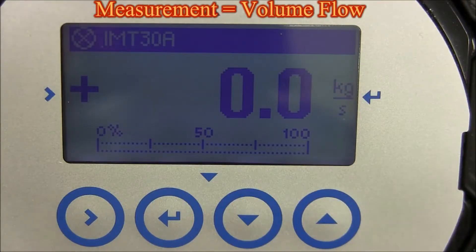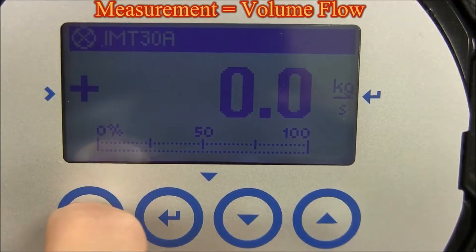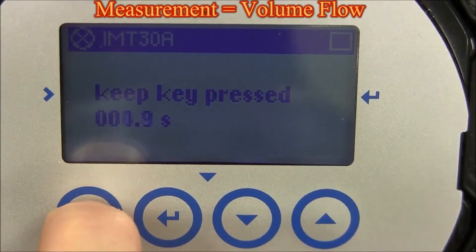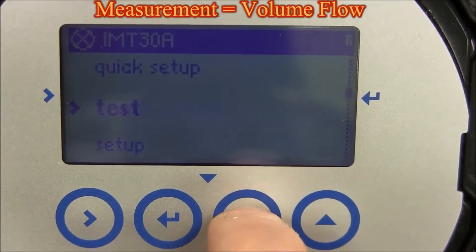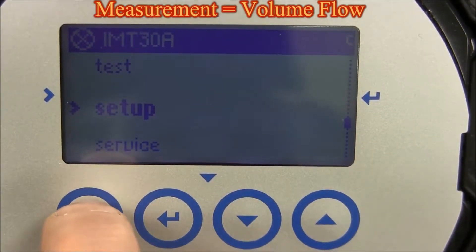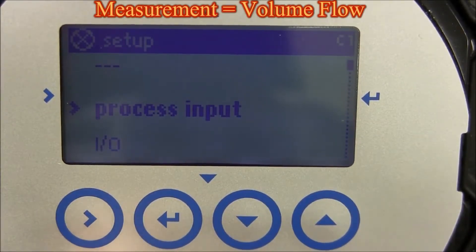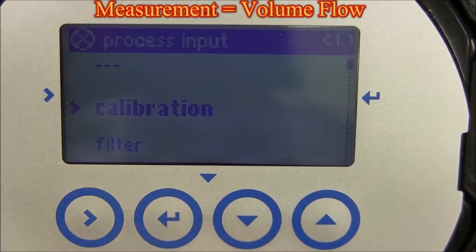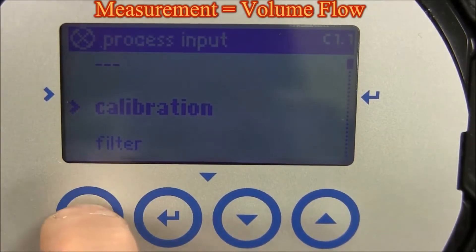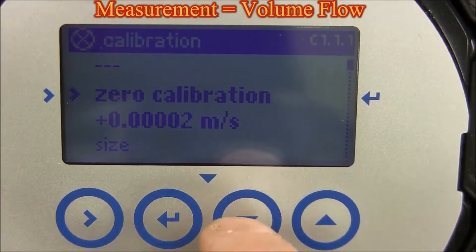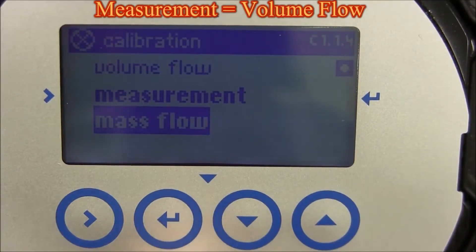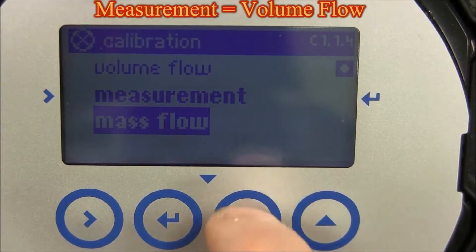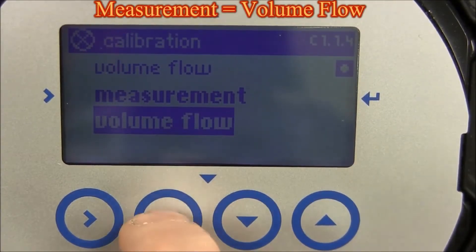To select volume flow for the measurement parameter, press and hold the right arrow for three seconds, then let go. Press the up or down arrow until setup appears, then press the right arrow. Press the right arrow to go into process inputs. Press the right arrow to go into calibration. Go up or down until you see measurement, then press the right arrow. Press the up or down arrow until volume flow appears.